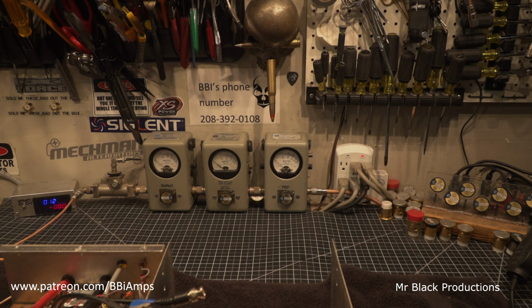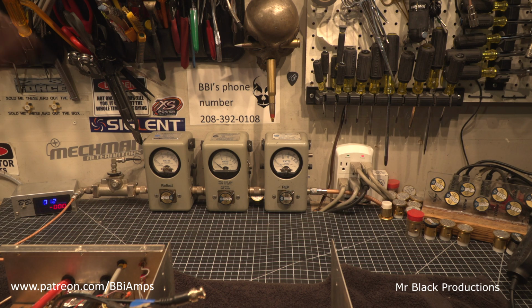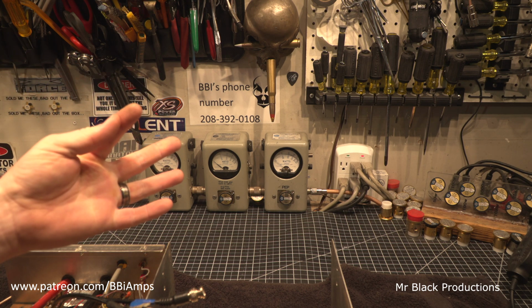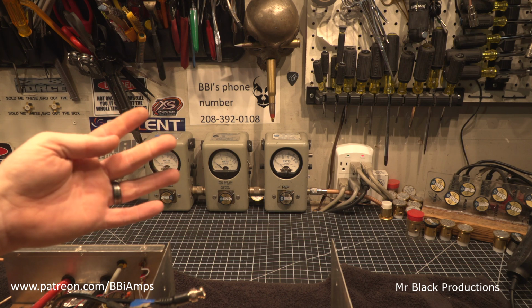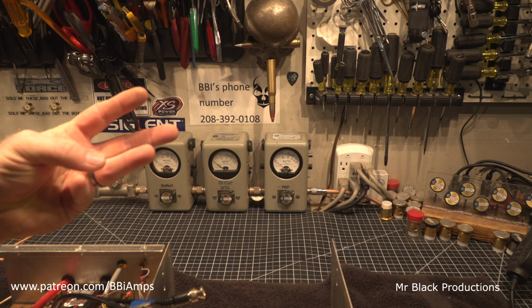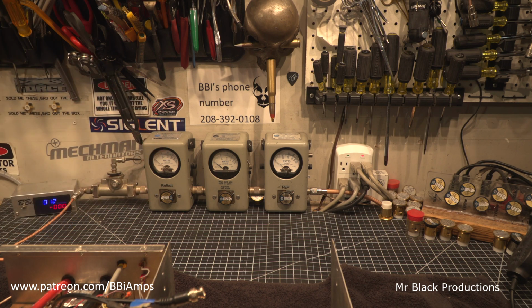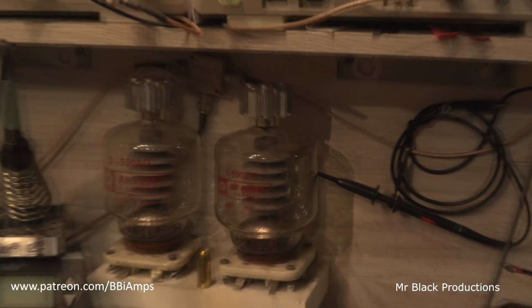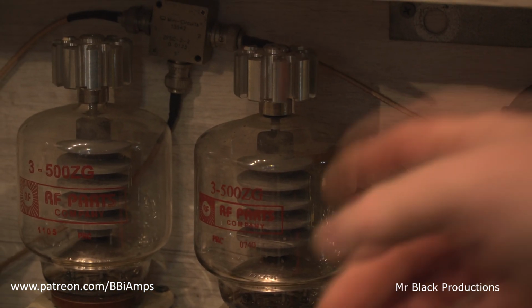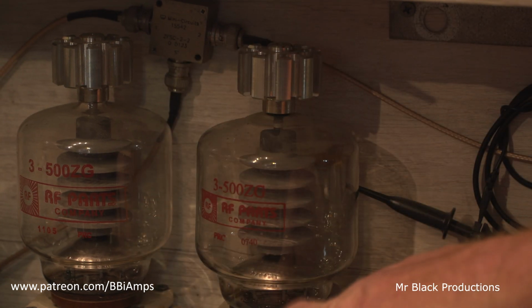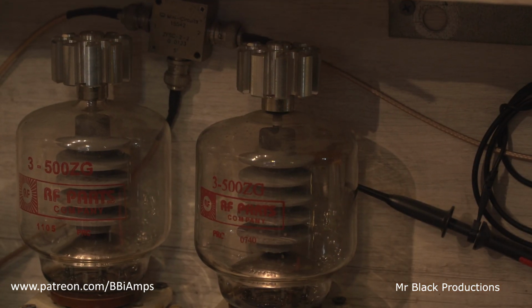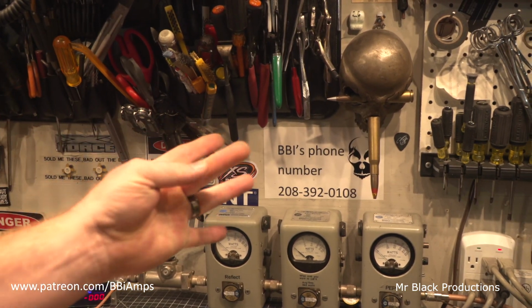Let me jump back in here and say that there's a couple other technical things that we have to discuss. So you have your filament transformer, which has got your one leg and then your other leg, the 2.5 and 2.5 volts. Well, there's actually 3 legs on that filament transformer. You've got your 2.5, your 2.5, and then your 0 center tap. So you have your anode, which is the upper portion of this tube structure, and then you have your cathode, which is at the bottom side of the tube and on the inside. The only way you can have access to the cathode to do anything inside the tube or control the tube is through that center tap on the filament transformer, that center leg.